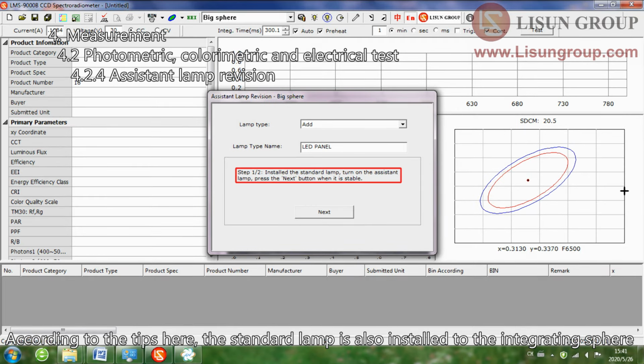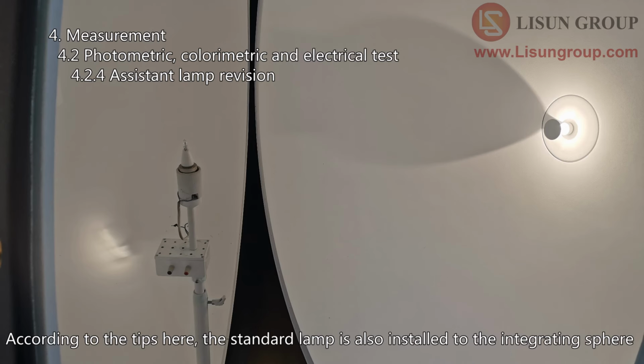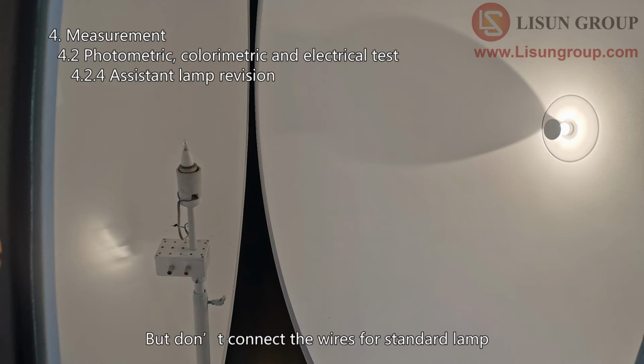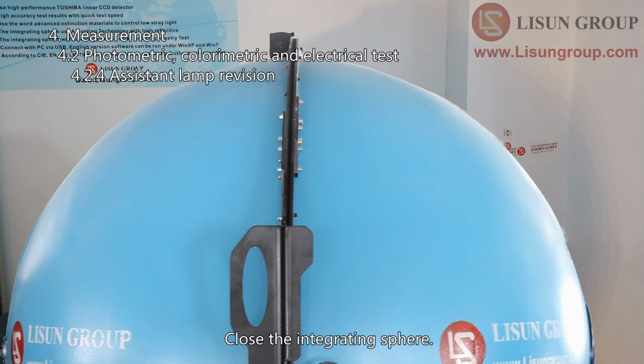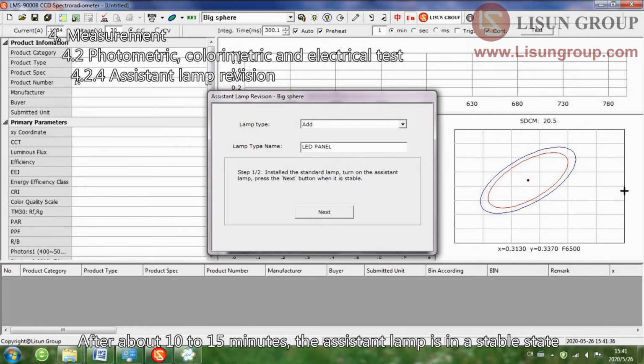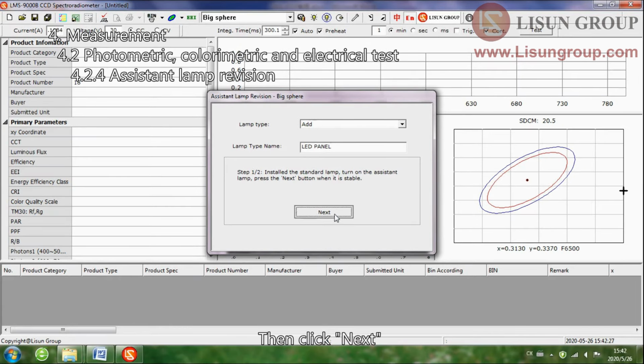According to the tips here, the standard lamp is also installed to the integrating sphere, but don't connect the wires for the standard lamp. Close the integrating sphere. After about 10 to 15 minutes, the assistant lamp is in a stable state. Then click Next.